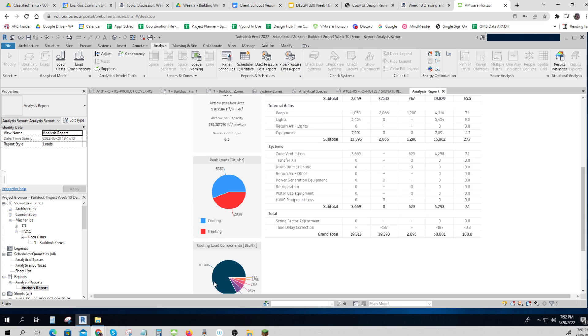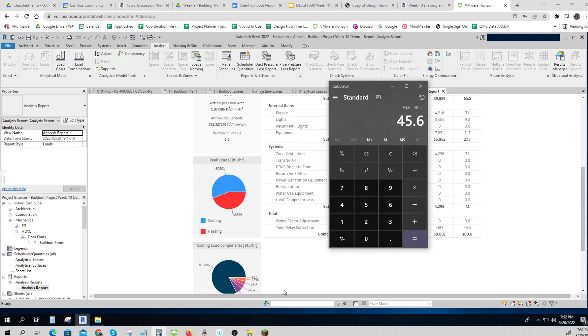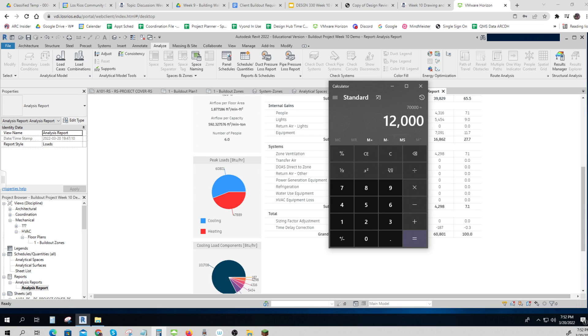Okay, so I need to have my calculator up. Let's say it was 70,000, it's not but let's pretend it was, divided by 12,000. I would need 5.8 tons. Well, they don't make 5.8 tons, I'll have to go with six.